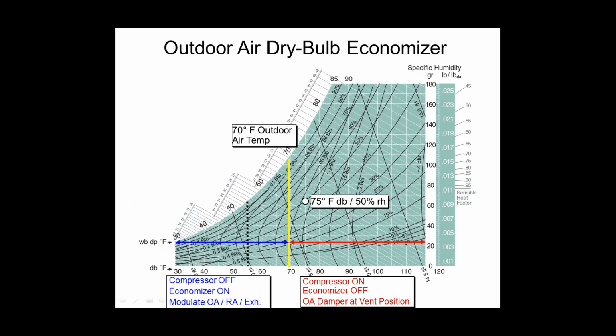So it wouldn't be a PDH seminar if we did not have a psychrometric chart involved. For you guys that aren't familiar with psychrometric charts, don't freak out. Hopefully you can see my pointer mouse thing here, right? So the psychrometric chart on the bottom scale, that is your dry bulb temperature from left to right, going low to high, 30 to 120 in this case. Up the vertical scale is your indicator of moisture content. The curved lines going all the way through the graph here are your relative humidity, right? It's relative humidity because it's not direct humidity like over here. It's relative to how warm the air is.